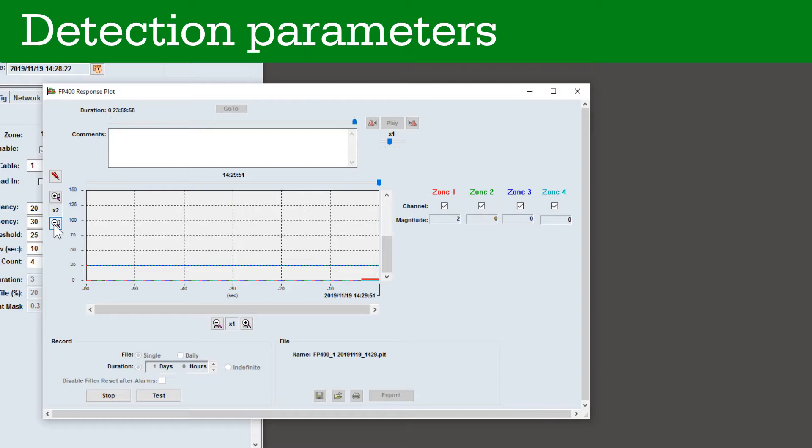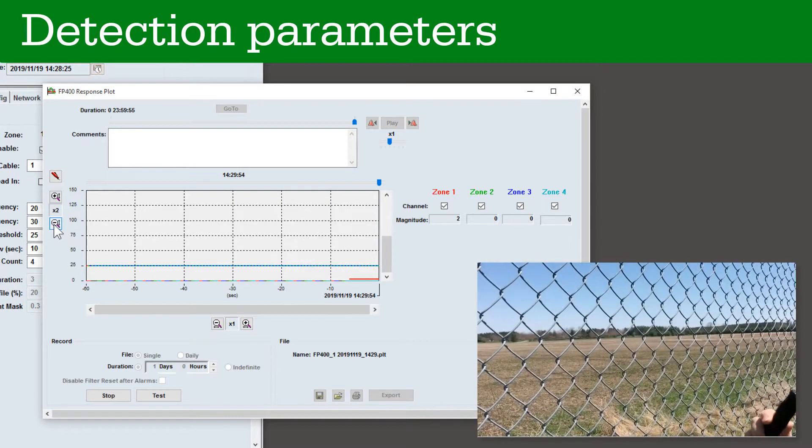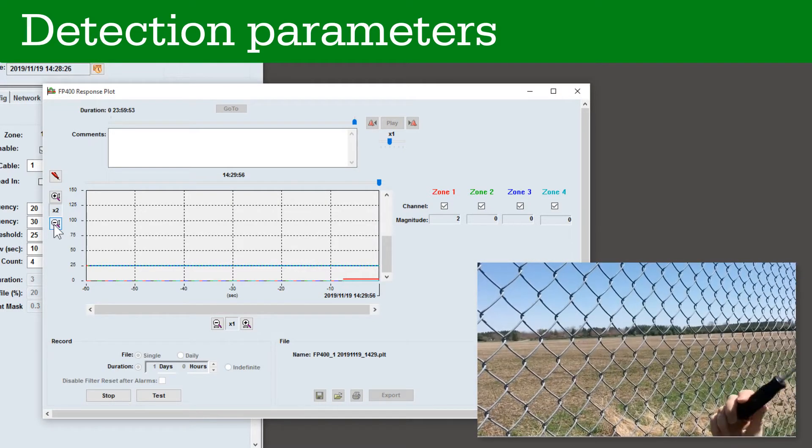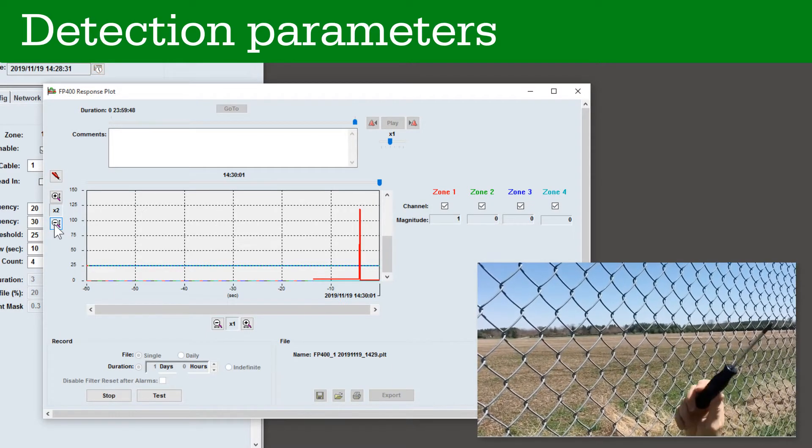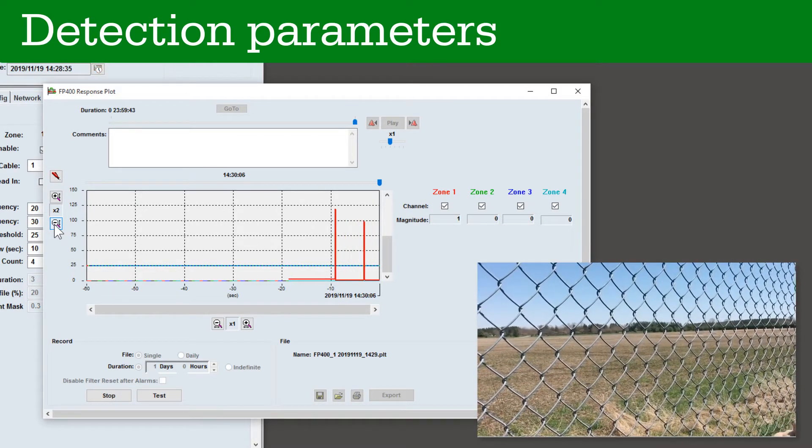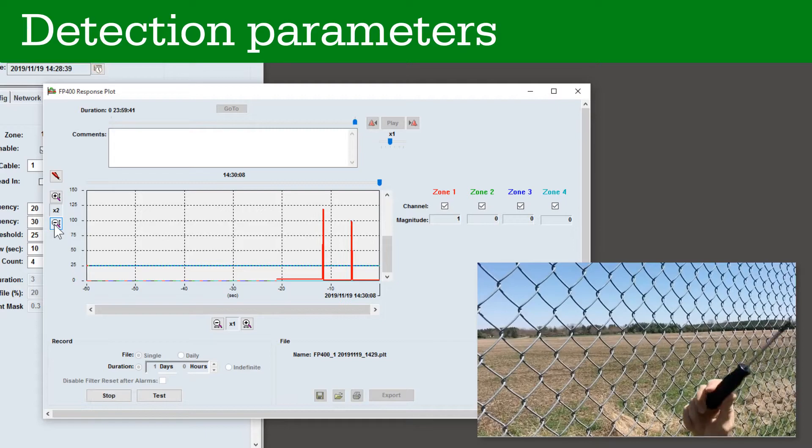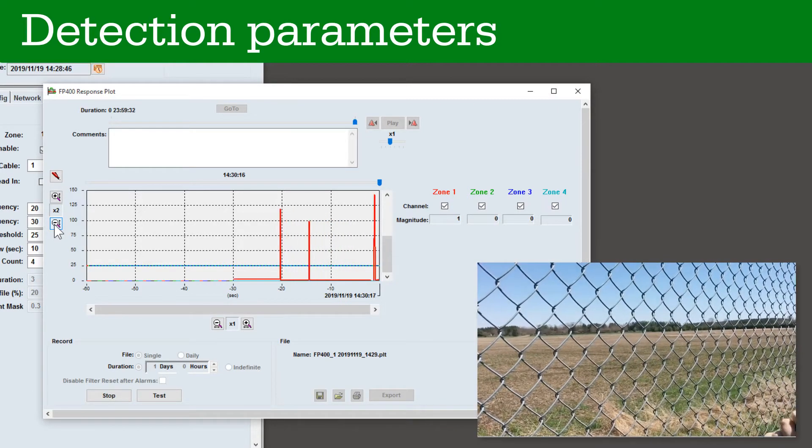Simulate a fence cut by tapping several times on the fence using a screwdriver or other heavy object, waiting three seconds between taps. Each tap should make an audible clink sound. Observe the response plot.